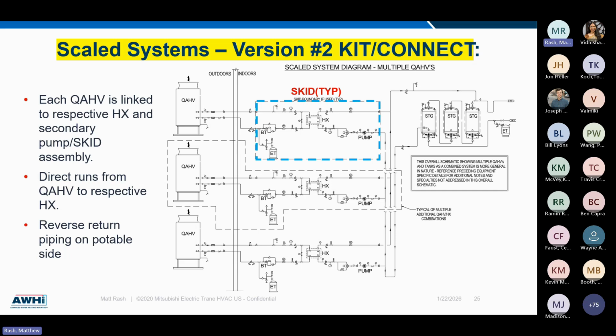And then again, based on cost or needs or logistics, if they want to go to a piecemeal version, we have that as well. And that's going to be the kit. So again, the Connect and the kit are identical in capability, functionality. It's just based on upfront cost and preference for what's needed for the project. Each of these also require a tank temperature control panel. That's what's going to monitor temperature in those tanks and then make the decisions with regard to staging lead lag operation of the individual skids or the kits.